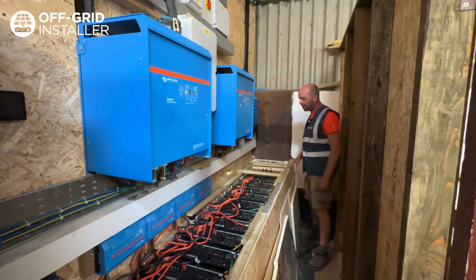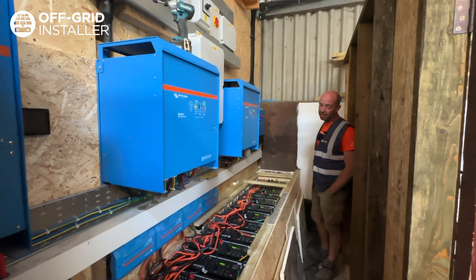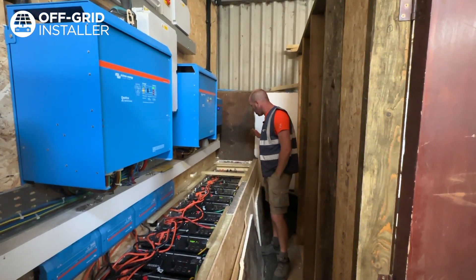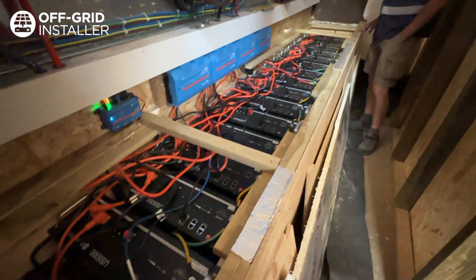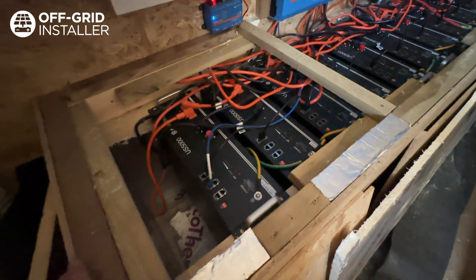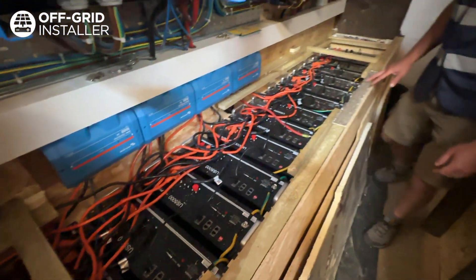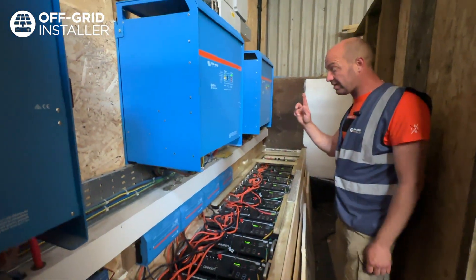Right, here we are in the plant room. We've just completed a three-phase ESS energy solar storage. Here, ladies and gentlemen, we've got 16 4.8 kilowatt hour batteries, all paralleled up in twos. Obviously there's a lot of DC cables on this — it is a very big battery bank. It is 76.8 kilowatt hours to be precise.